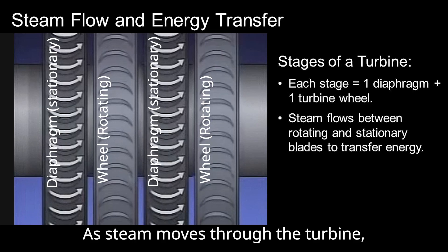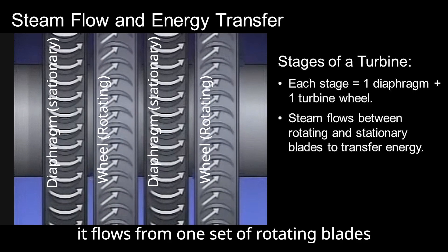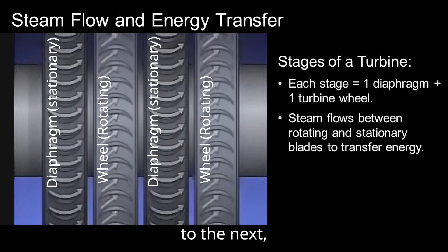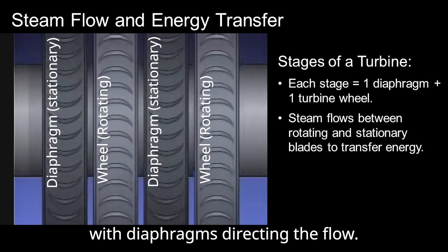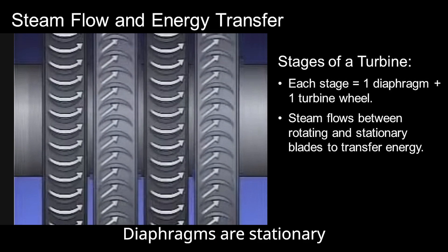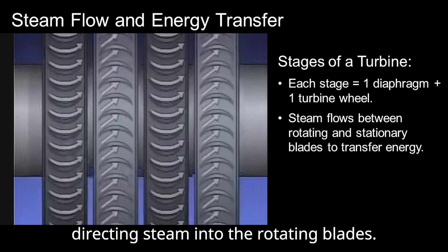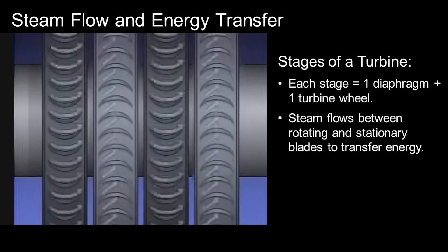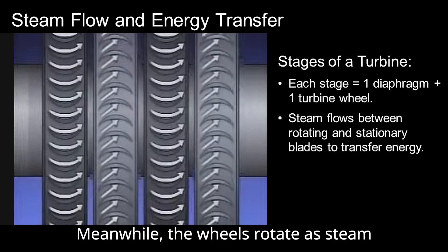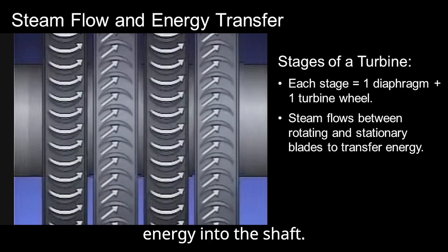As steam moves through the turbine, it flows from one set of rotating blades to the next, with diaphragms directing the flow. Diaphragms are stationary and act as guides, directing steam into the rotating blades. Meanwhile, the wheels rotate as steam strikes the blades, transferring energy into the shaft.